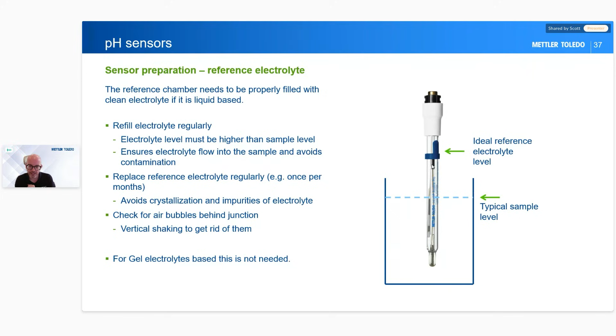You can also use a little bit of warm electrolyte, so 40 degrees, to try and wash it out as well. If there's lots of crystals in there, it's hard to dissolve. But don't use anything too hot because we don't want to, yet again, stress the electrode. Once we've done that, we just give it a quick flick like a thermometer, and we get rid of all the bubbles inside and it's ready for measurement. The other thing is if we do refill it, we've got to make sure that we refill above our level of sample. Because if we go below that, we'll end up with sample coming into our electrolyte, which we don't want. We want to keep the level high to keep the pressure high.